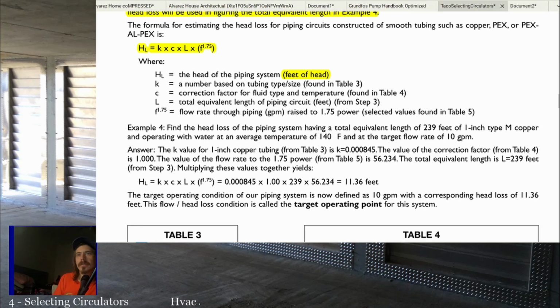Glycol changes the density of the fluid in it too. L is the total equivalent length of the piping circuit. That's what we just learned to figure out, right? And F to the power of 1.75 is the flow rate of the piping system up to the 1.75 power. So that just tells us how fast the fluid is moving through it, right? Based on all these, this is going to account essentially for the extra friction of the water moving at a high speed.